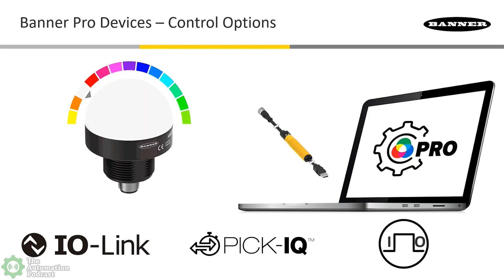You can see one very common protocol on the screen — IO-Link — along with a couple of other options. How do you see machine designers and automation engineers interfacing with this type of equipment? I think IO-Link is becoming preferred over standard discrete IO because if you had several different states, you could use half an IO card to interface to this device. Whereas with IO-Link, it's still one point on a card, but now we can send down the information, the trigger, and what we want to do. IO-Link for smart devices like this would probably be a top choice.